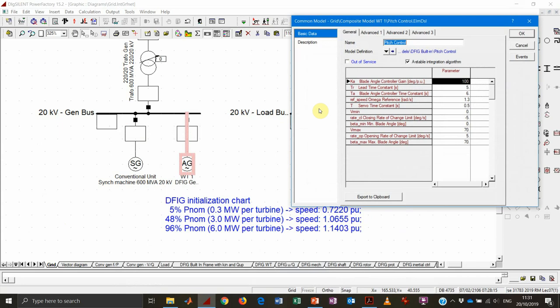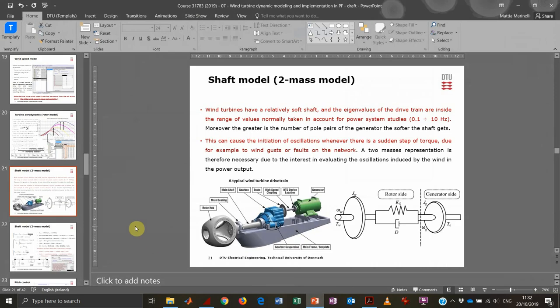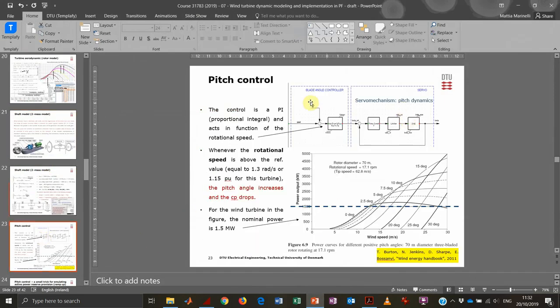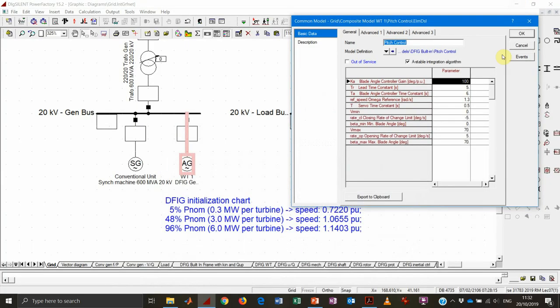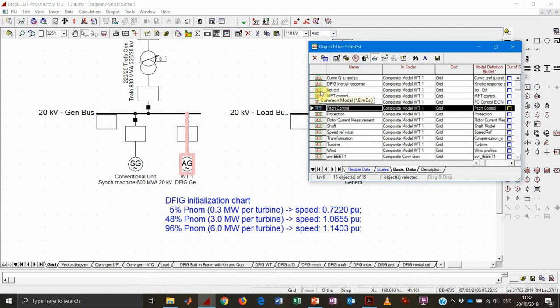The pitch control block models the dynamics of the control logic behind the pitch control system activation. It is a fairly simple proportional-integral controller activated according to an error between measured speed and the reference rotational speed, and it also models the actuator dynamics — how quickly the blades can pitch in and out in degrees per second, and the pitch angle range: in this case from zero degrees minimum up to 70 degrees.